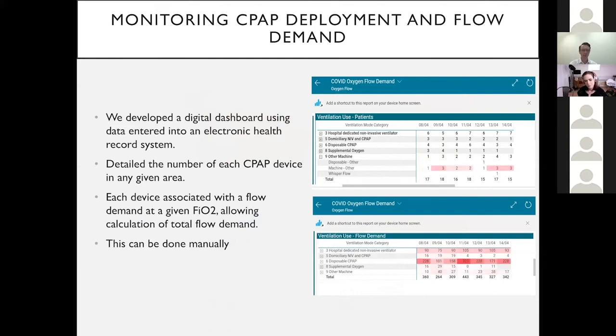Understanding the flow capacity for our ward environment and the flow demand of our various CPAP devices, we could build a system which allowed us to monitor the flow demanded in our ward environment. We did this digitally because we have an electronic health record system that allows that, but there's no reason it can't be done manually, although it's a bit more labor intensive. This was really useful for me when trying to run a ward through this pandemic, so that I could understand, at any time of the day, what flow was being demanded in any given CPAP ward area, allowing me to step in should the flow demand increase anywhere near a limiting level.